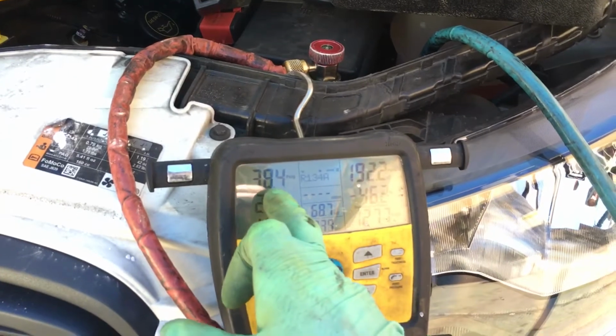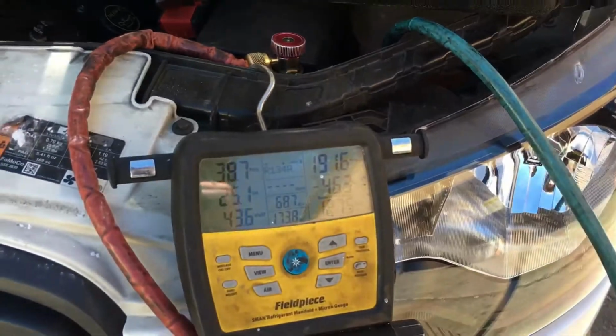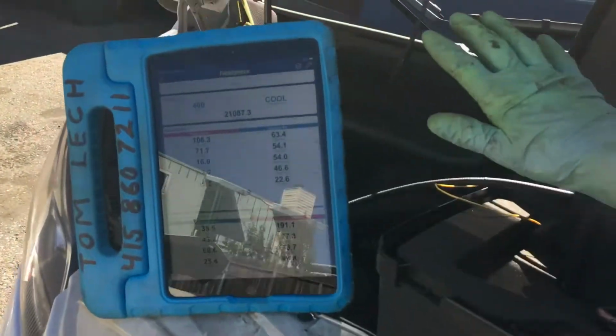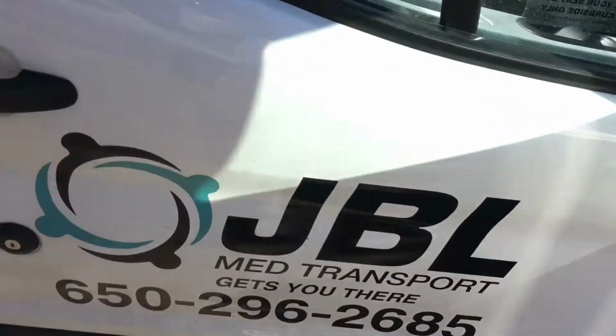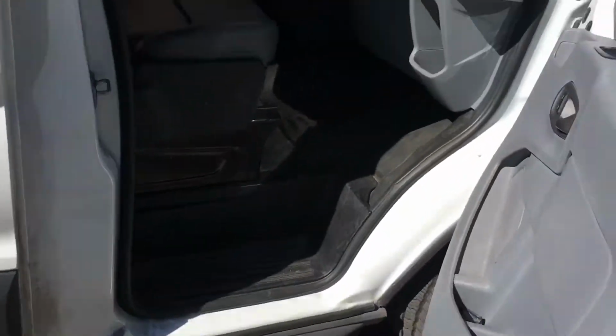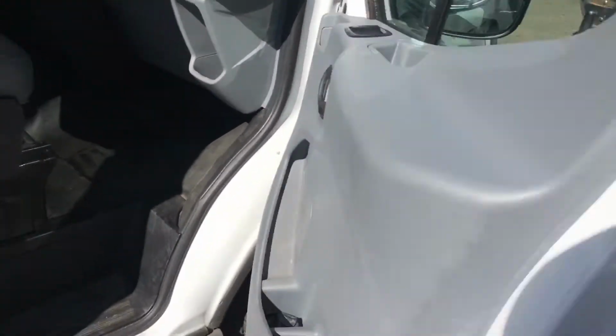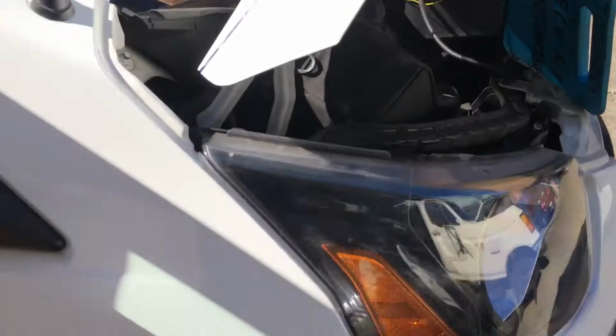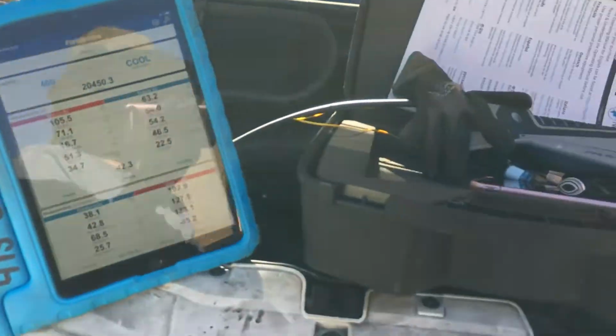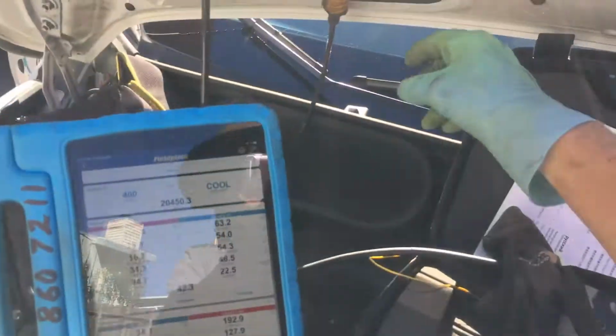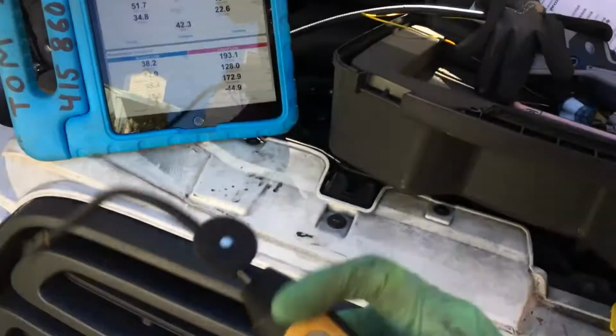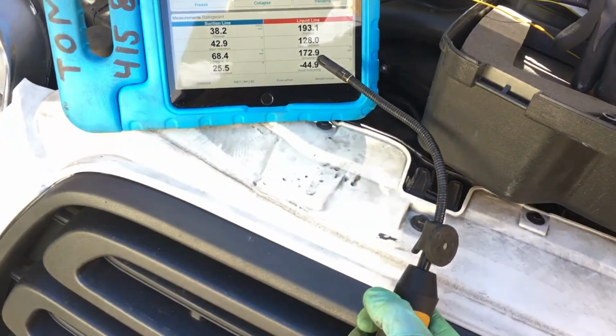And we were at like 41, 40. We only came down to 30. But I just unloaded it. I had 115 degrees going in over the evaporator, and now I have roughly 72 degrees air going from recycling up under right over the evaporator with no load, and we're still way up there. What's going on? This is the question. So let's take this temperature sensor here. So we're going to take this right there to 172 degrees.